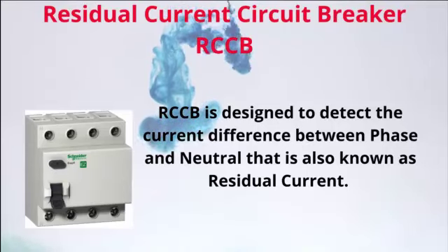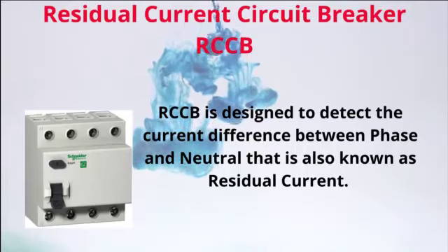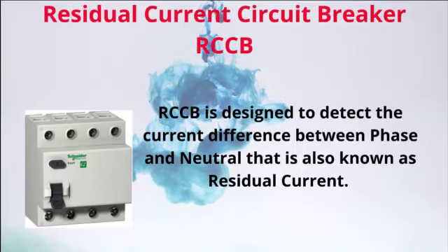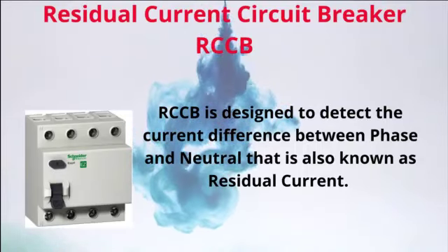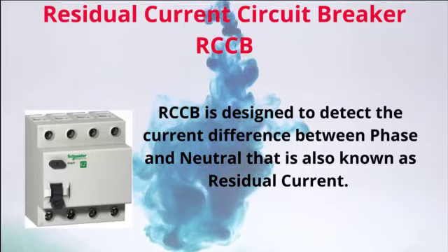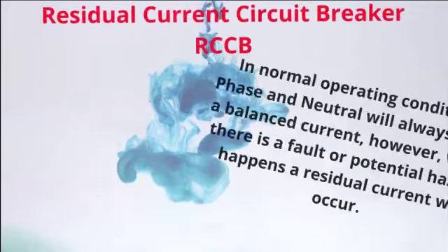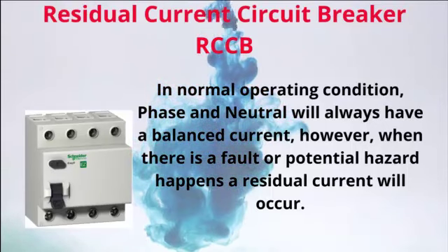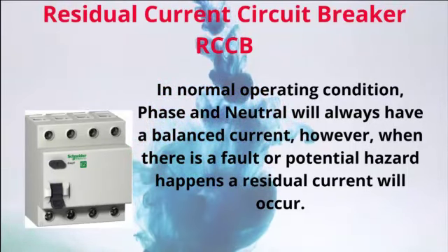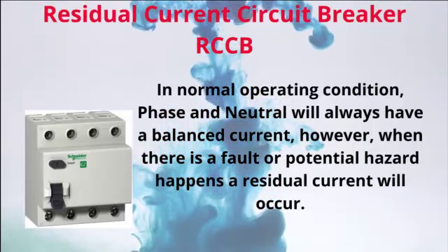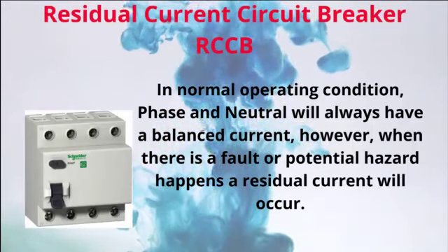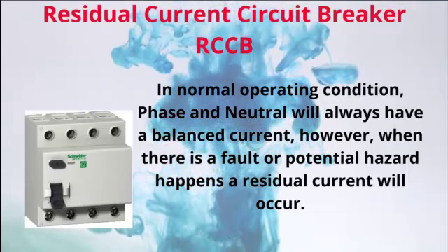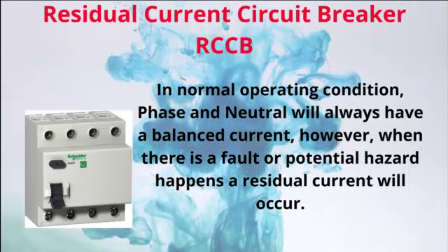RCCB, residual current circuit breaker. RCCB is designed to detect the current difference between phase and neutral, that is also known as residual current. In normal operating condition, phase and neutral will always have a balanced current. However, when there is a fault or potential hazard, a residual current will occur.